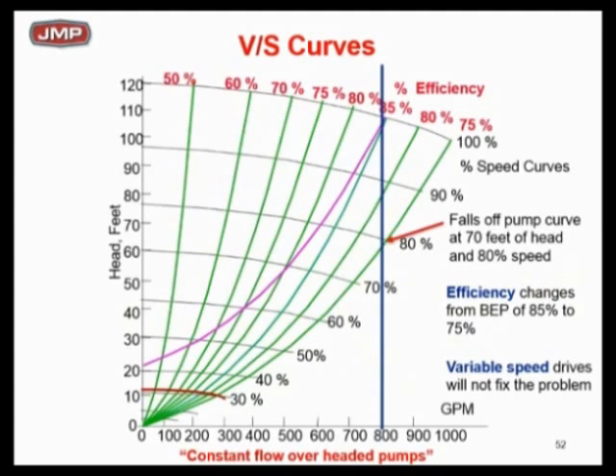Let's go back to the same pump curve: 800 GPM, 110 feet of head. Let's assume it's a condenser water pump where I want constant flow of 800 GPM, or a hot water or chilled water system with two-way valves at full load — which only happens about 1% of the time, but it will happen. In other words, let's look at full flow: I need 800 GPM.